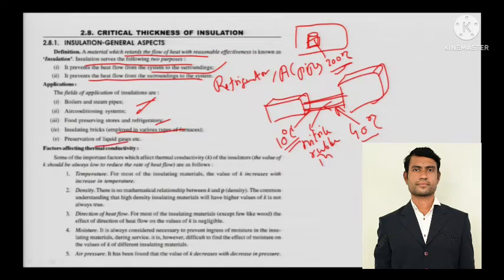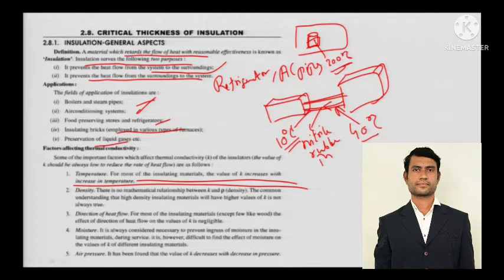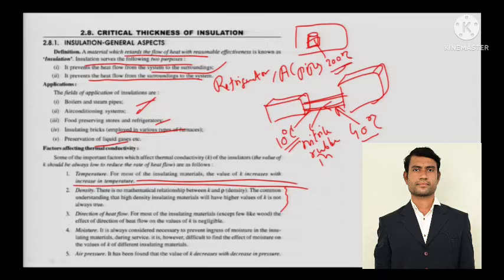Factors affecting thermal conductivity: the value of k should always be low to reduce the rate of heat flow. Temperature — for most insulating materials, the value of k increases with increase in temperature. This is a very important point. Density — there is no mathematical relationship between k and density (ρ); the common understanding that high-density insulating materials will have higher values of k is not always true.